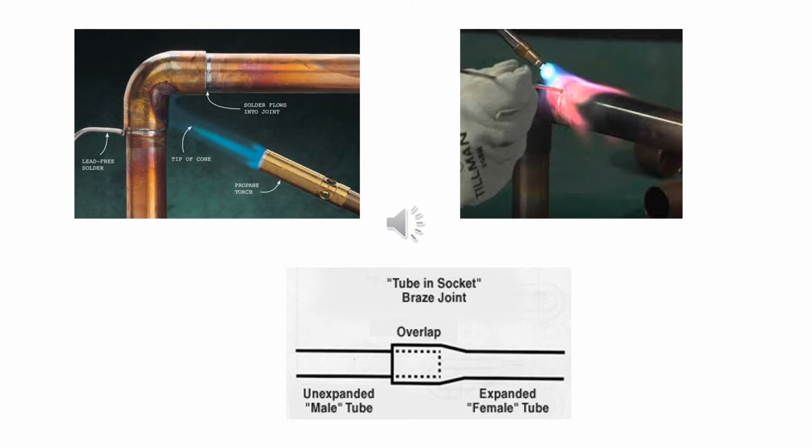Hard-drawn copper pipe is usually joined by soldering or brazing with fittings. Soft copper tubing can be joined by the same techniques. It is also possible on soft copper tubing to expand the end of one tube so that it can be joined to another by soldering or brazing without a fitting, a procedure that can be efficient and economical in many installations and is known as swedging.